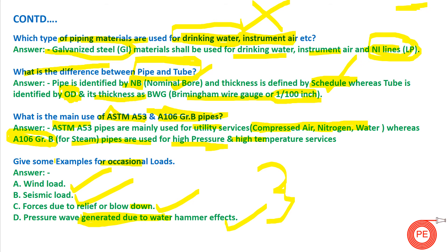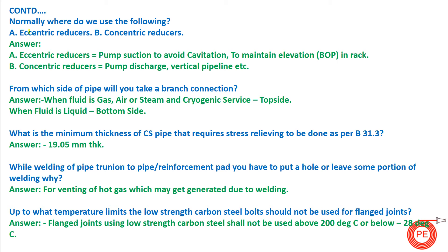Normally, where do we use eccentric reducers and concentric reducers? Eccentric reducers are used at pump suction to avoid cavitation and to maintain the bottom of pipe (BOP) elevation in pipe racks. They also help eliminate air bubbles entrapped in pump suction. Concentric reducers are used at pump discharge and in vertical pipelines.